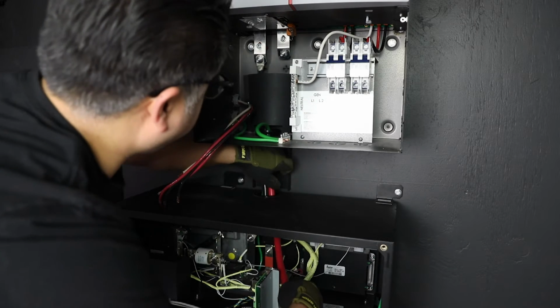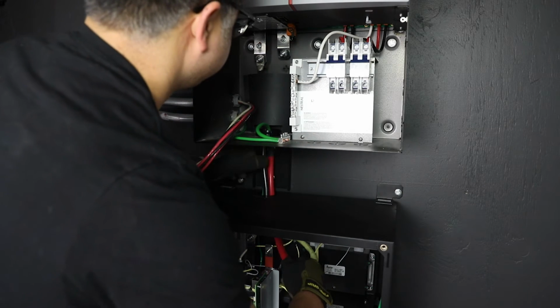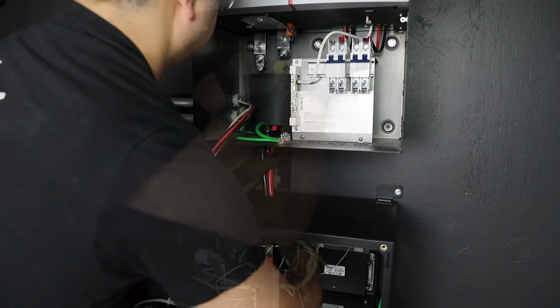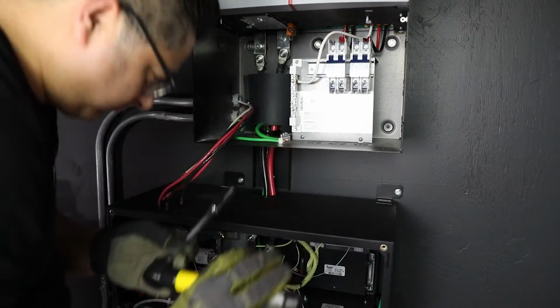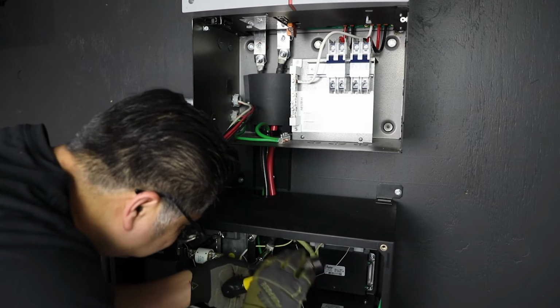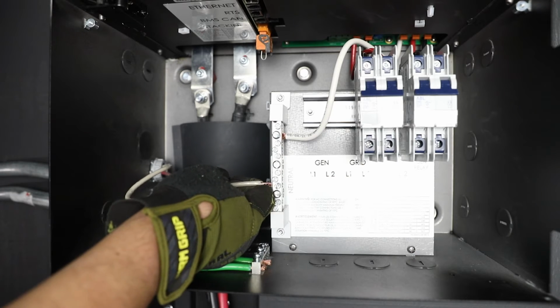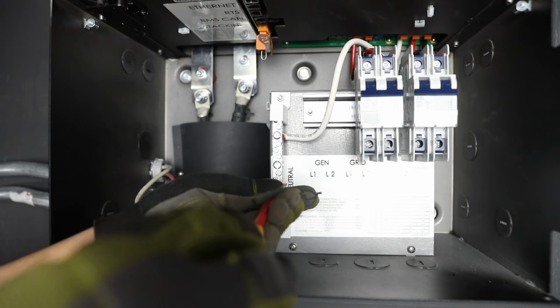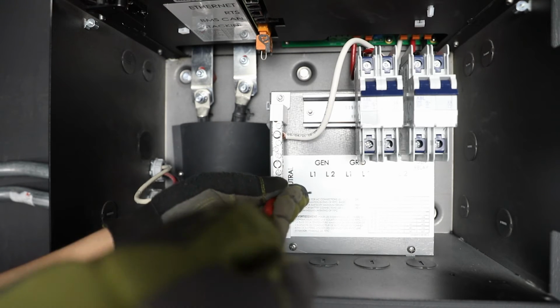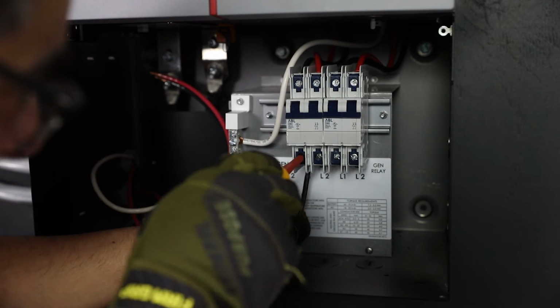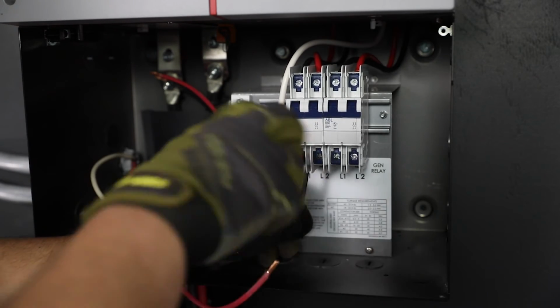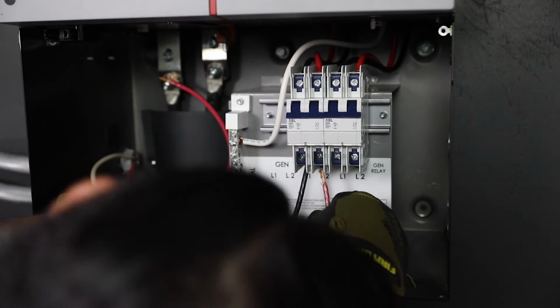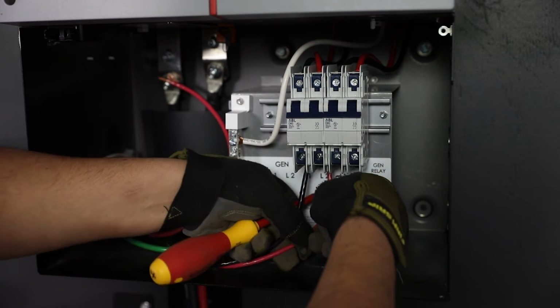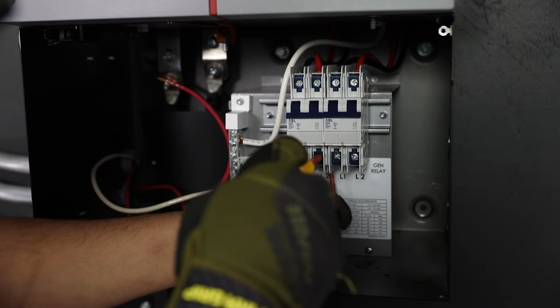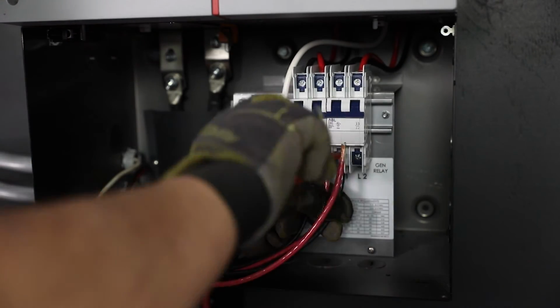Route the positive battery conductor through the battery, raceway, and underneath the inverter's plastic shield to the right DC plus busbar and connect. Connect all AC neutral wires, including grid, load, and generator if it applies. Connect grid input L1 and L2. Connect load L1 and L2.